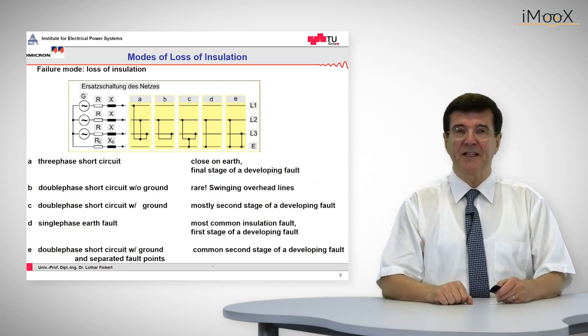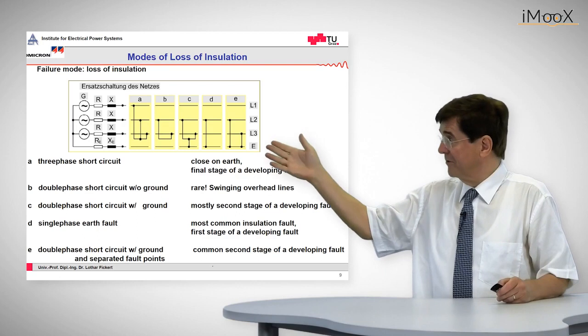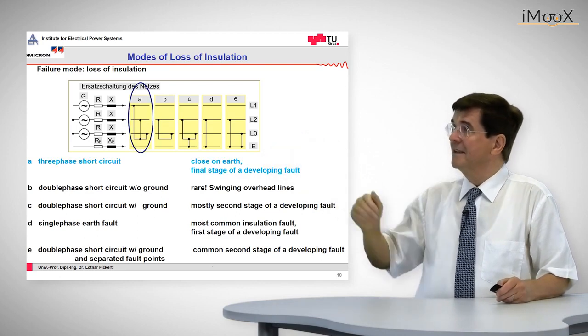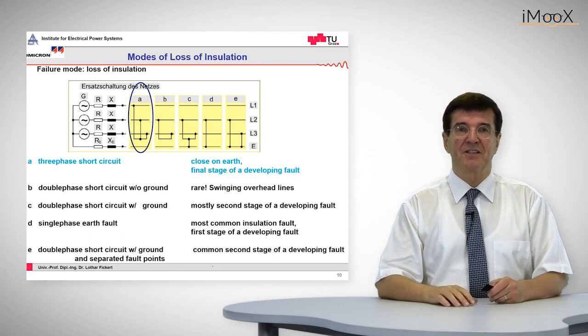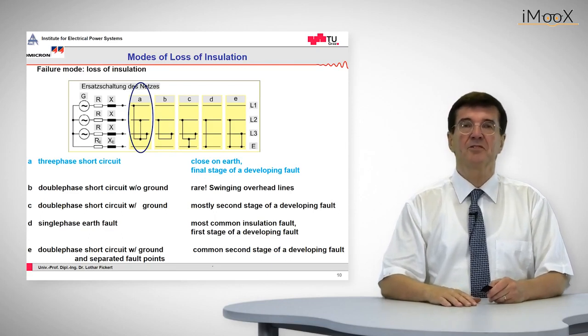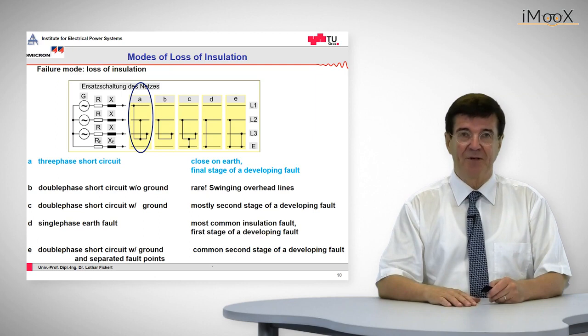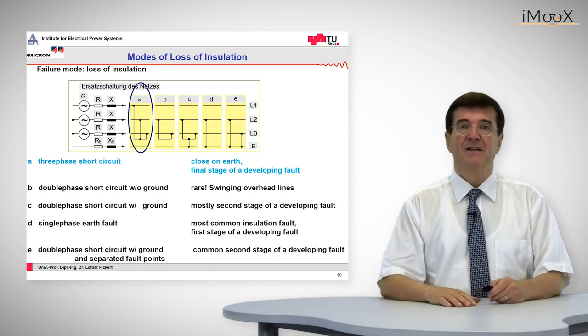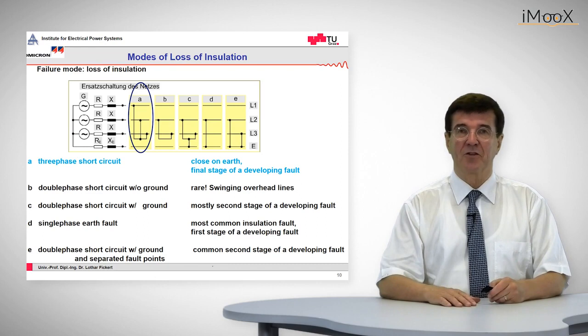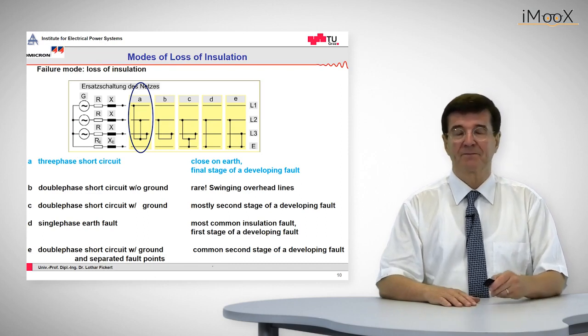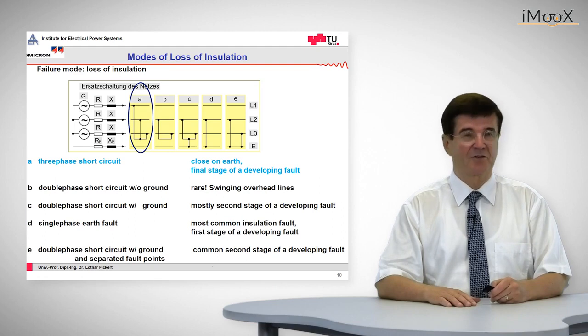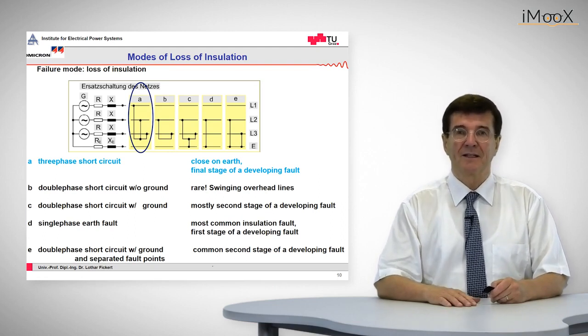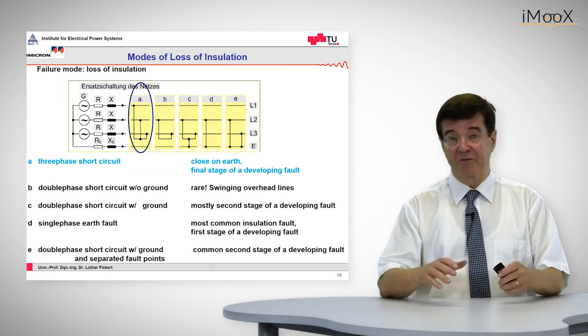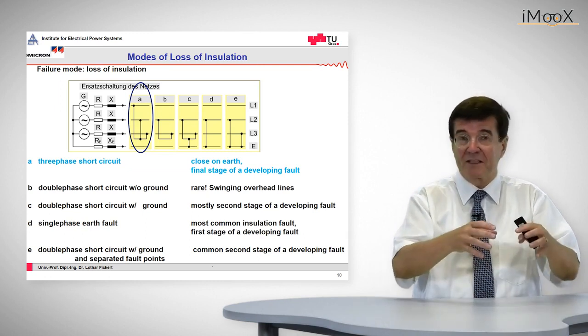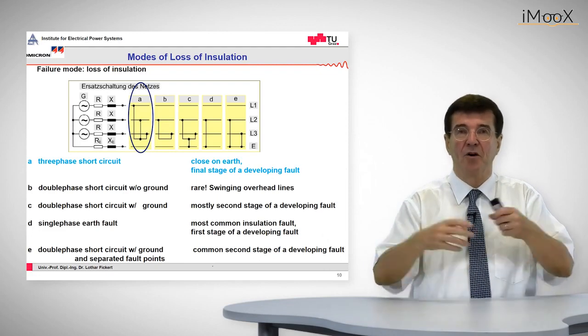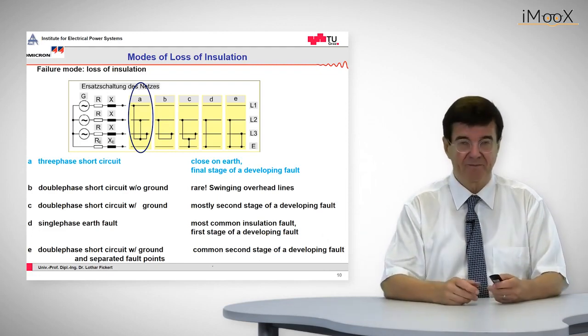The classic classification of these is, as we can see, to my right side. So let's start with fault class A, which is the three-phase short circuit. This is the easiest one to calculate, but in reality it is very rare. Three-phase short circuits normally occur only either by closing on ground, that is a switching error, or at the last stage of a developing fault. A developing fault starts as a single or double phase fault and the arc burns until the whole thing ends up as a three-phase fault.